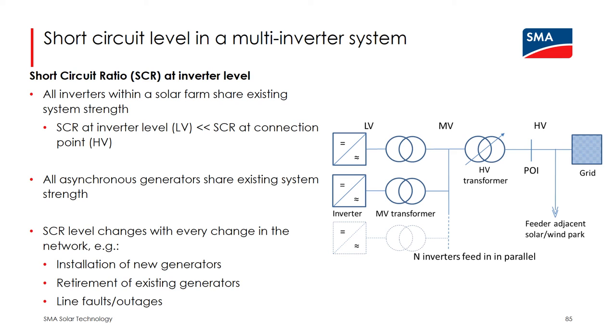Another aspect which is quite important to understand is that if several generators are connected in parallel in a network, those generators are sharing the existing system strength, or the existing short circuit level, at this point. So this gives you a good idea that with an increasing number of asynchronous generators getting connected to the network, the overall short circuit ratio keeps decreasing. And this is even accelerated by the retirement of existing synchronous generators over time.